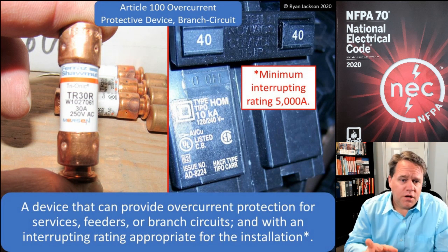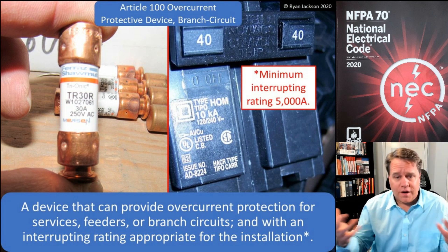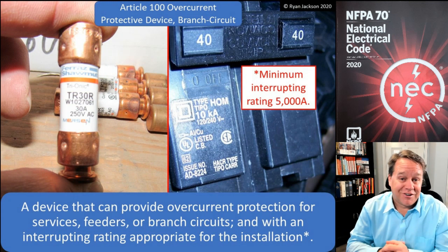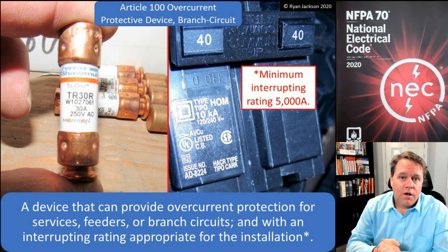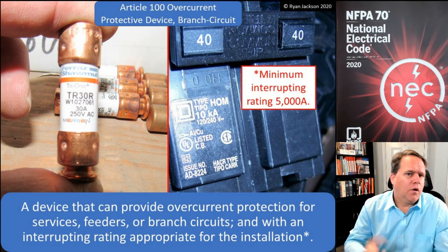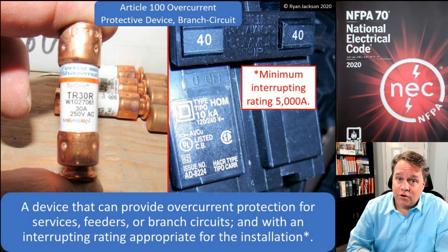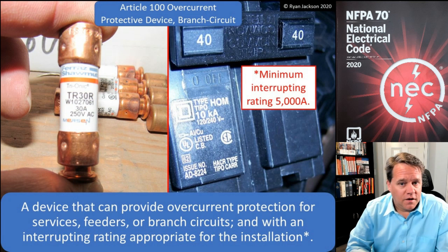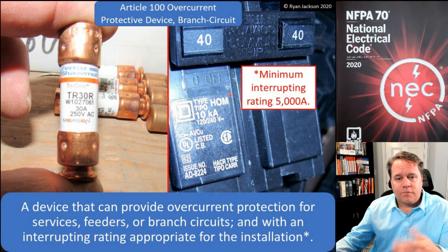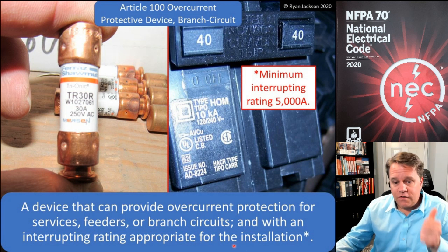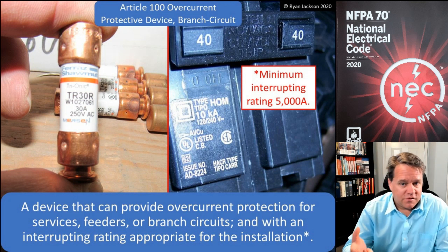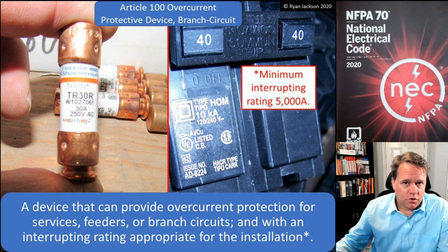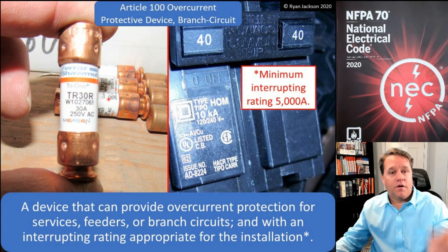Usually we use one device to protect against all three forms of overcurrent. For example, a bathroom circuit has a 20-amp circuit breaker. If you plug in five hair dryers and a curling iron, that 20-amp breaker trips — that's an overload. If you cut the cord on your hair dryer while it's plugged in, that's a short circuit or ground fault, and that also trips the 20-amp breaker. A branch circuit overcurrent device provides protection for services, feeders, or branch circuits and has an interrupting rating never less than 5,000 amps.